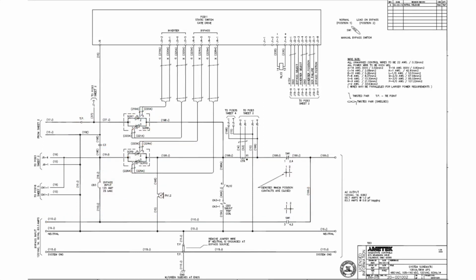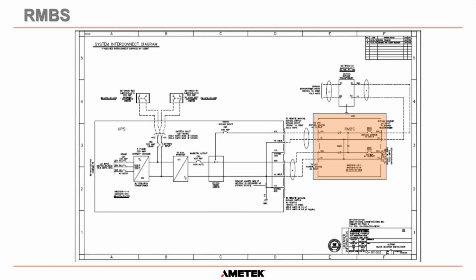So that's on a manual bypass switch. But remember, this switch is on the UPS itself. So that means we are going to have power going to the contacts of these switches. So that means the UPS cubicle is not going to be completely volt free. And in those circumstances, if any of our field service guys come out and have a look at your system, we'll take an insulated blanket with us, and we'll cover those terminals to make sure there is no exposure to live terminals or arc flash. So you can see that it's not the best situation because we still have power in the UPS. So what we recommend you do, as I mentioned earlier, is get an RMBS.